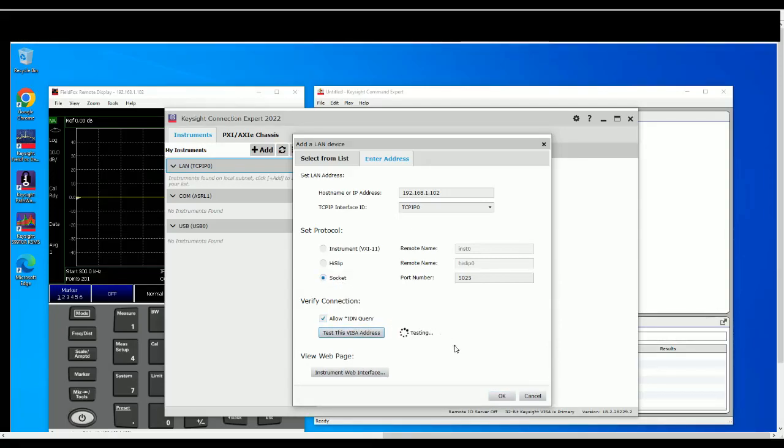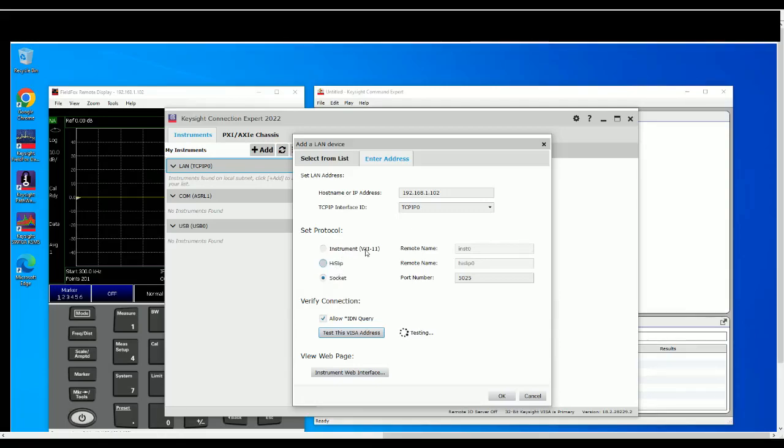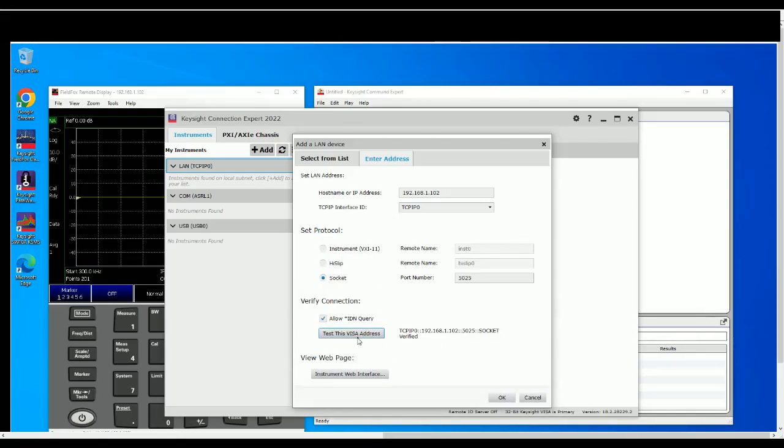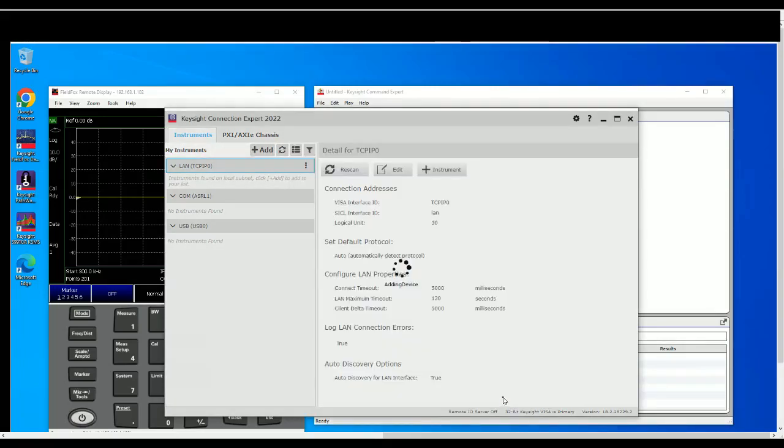So because we are using SCPI command via socket, so I do recommend to use socket and it all depends on the VISA library that you are using. PyVISA in Python is using socket method. I'm not sure about MATLAB, it could be HiSLIP or instrument VXI. So once you test this and verify it means that this instrument is ready to go, it's all connected correctly and you should see our instrument added here.